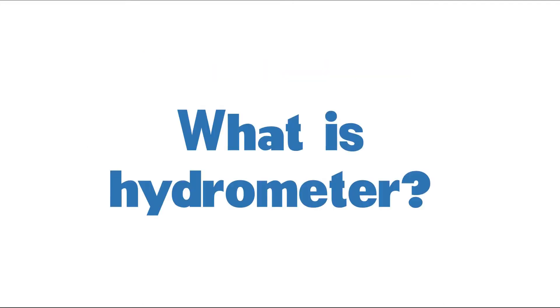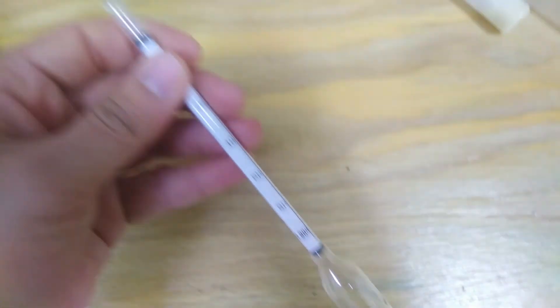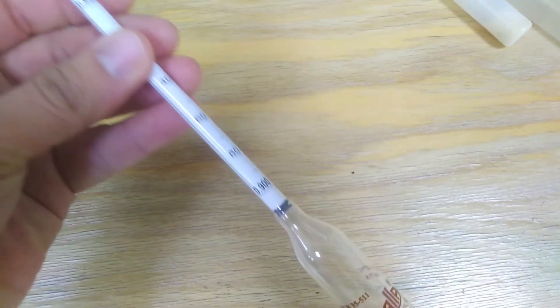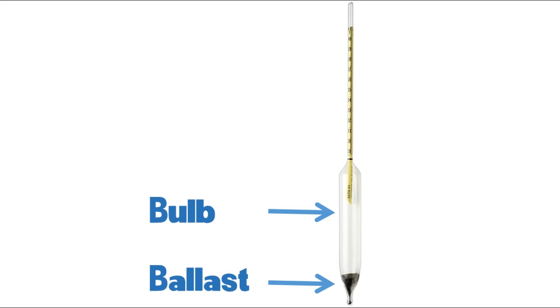Practically, specific gravity can be measured by a hydrometer. A hydrometer is a measurement device used to measure the specific gravity of liquids based on the principle of buoyancy. It usually consists of a sealed hollow glass tube with a wider bottom portion for buoyancy, a ballast at the bottom such as lead or mercury for stability, and a narrow stem at the top with graduations for measuring.